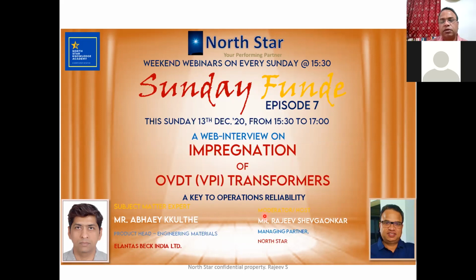In fact, our purpose of filtration is taking out the water or moisture from the oil. When you do the filtration, you are trying to remove the moisture. If you apply the vacuum, the temperature at which the moisture comes out from the transformer goes down. So if your vacuum level is say 1 millibar or lower, then the moisture can come out at a temperature around 50 to 60 degrees centigrade.